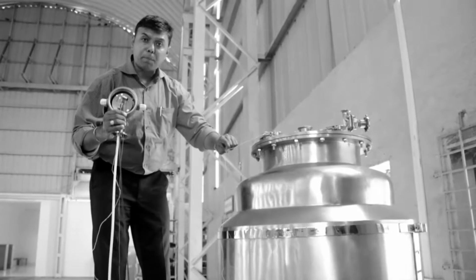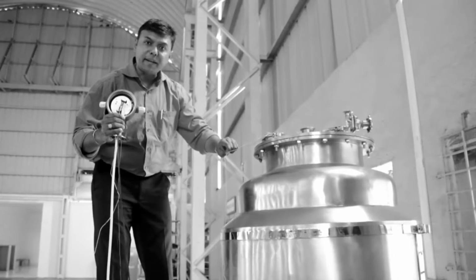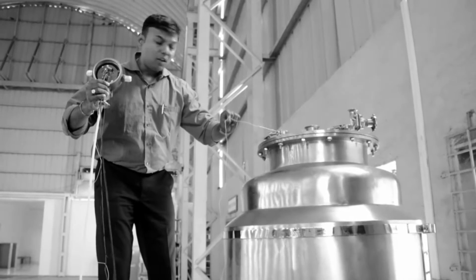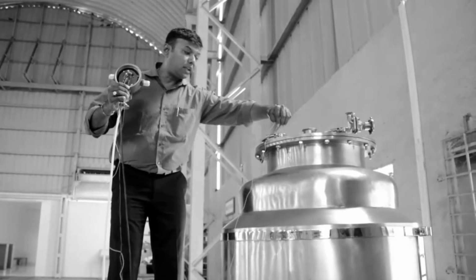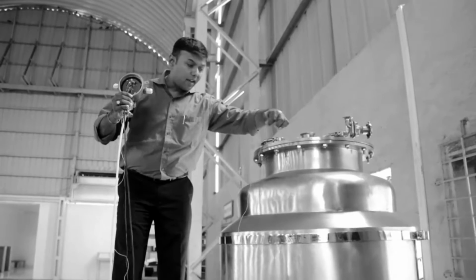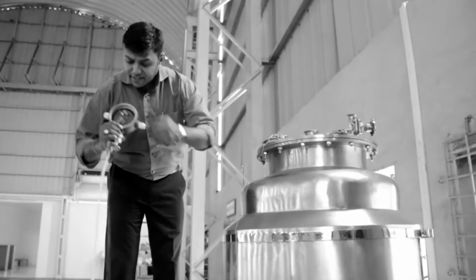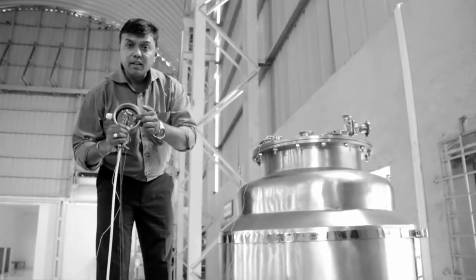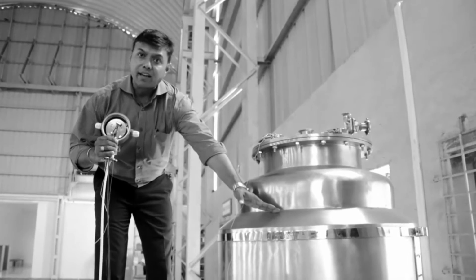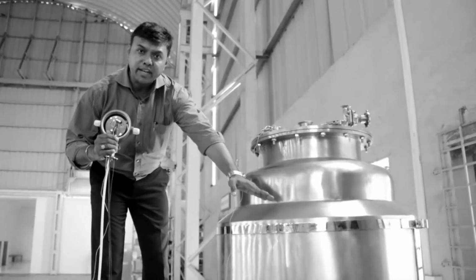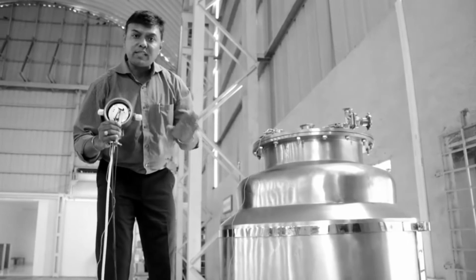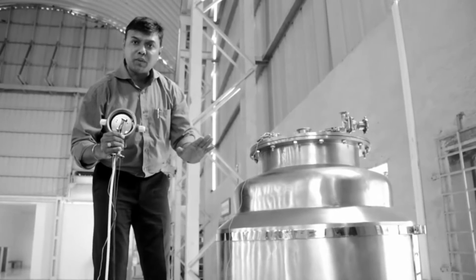Before you start the part 2 calibration process, I repeat again, connect a wire which will be connected to the body of the tank, and the other end of the wire should be connected to the negative of the terminal. Second, you have to fill up the tank. Fill up the tank till where you need the 20 milliamps. Now we start the calibration process once we are done with this.